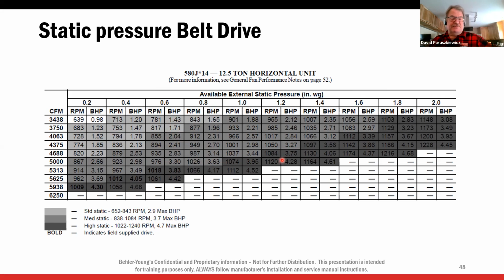So if you're checking temperature rise or you're checking temperature split, this was always an easy cheat we always did. And I just don't have enough airflow. And I cranked the thing up and it's cranked in all the way. I don't have enough airflow. Check your static. Take a look at this. Good possibility you need a higher static blower. The pulley's not going to change it. You have to change the motor.